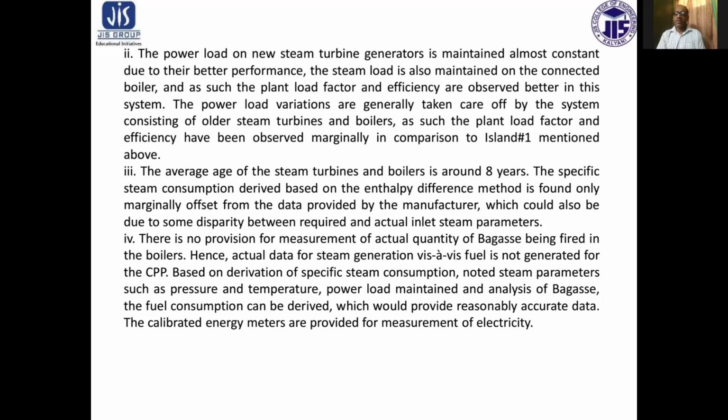As such, the plant load factor and efficiency have been observed to be marginally lower in comparison to island 1 mentioned earlier. The average age of the steam turbine and boiler is around 8 years. The specific steam consumption derived based on the enthalpy difference method is found to be only marginally offset from the data provided by the manufacturer, which could also be due to some disparity between required and actual inlet steam parameters.